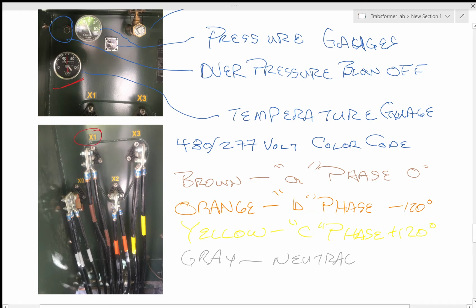X1 matches with H1, X2 matches with H2, X3 matches with H3, and as you saw, there were only 3 phases over there. Over here on the low side, you actually have a neutral, which is the gray phase right here. The gray phase is the neutral. Once again, you have a Y connected with a neutral, and they're 120 degrees out of phase.